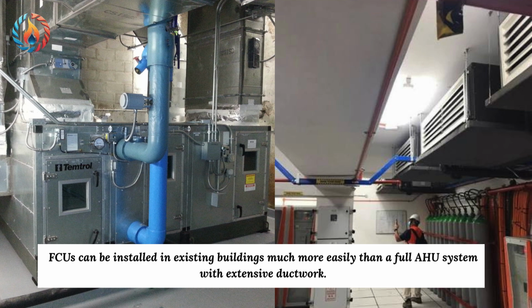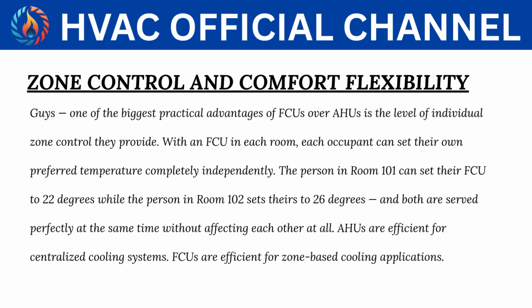Zone control and comfort flexibility. Guys, one of the biggest practical advantages of FCUs over AHUs is the level of individual zone control they provide. With an FCU in each room, each occupant can set their own preferred temperature completely independently.